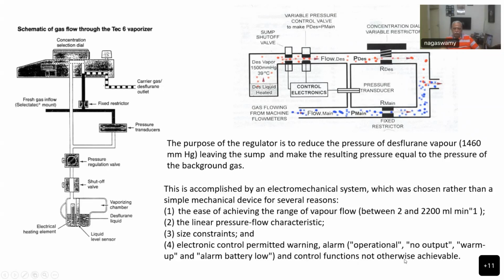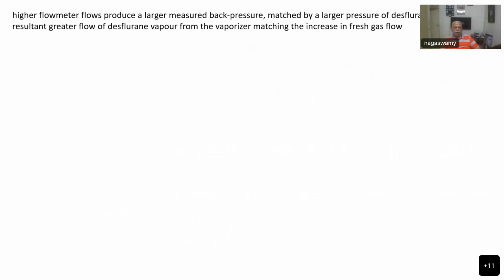So that is another reason why this output is mainly controlled by an electromechanical system. And the higher flow meter flows produce a larger measured back pressure, matched by the larger pressure of desflurane vapor, with the resultant greater flow of desflurane vapor from the vaporizer matching the increase in the fresh gas flow.